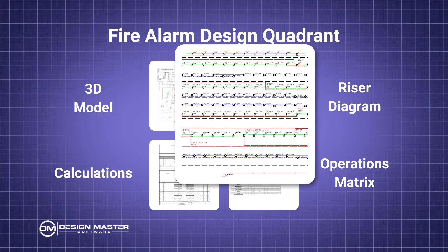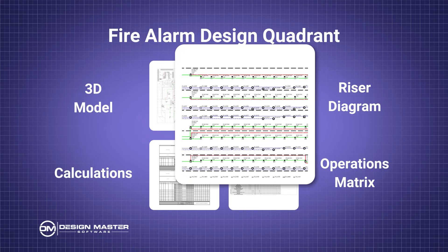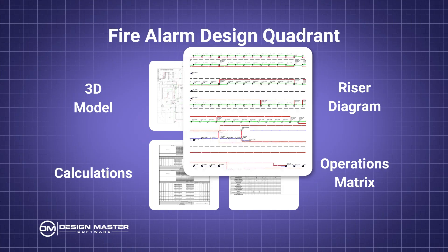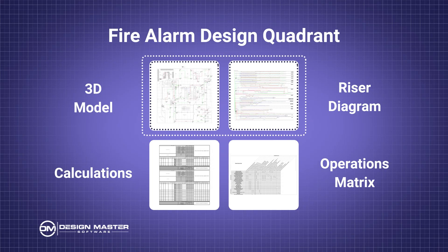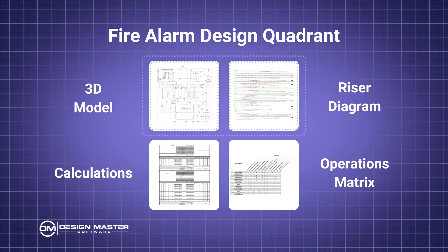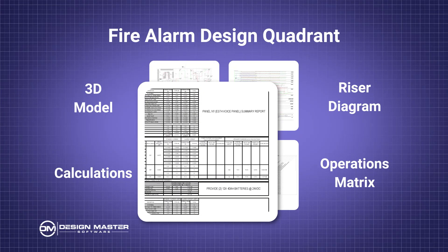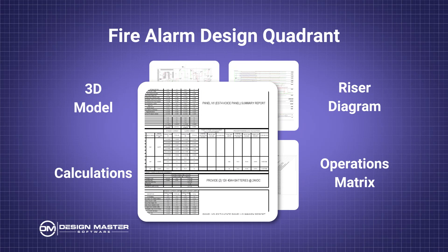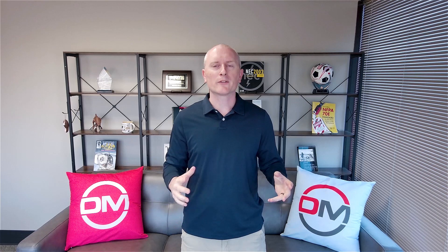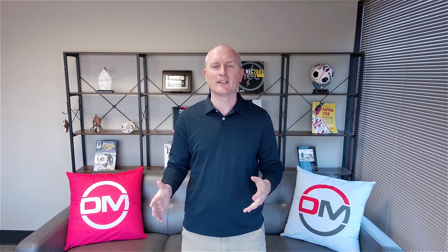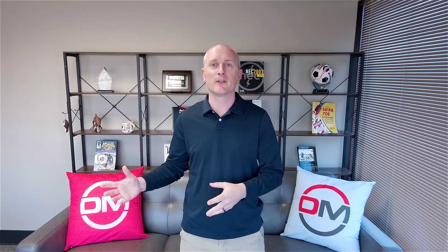The riser is a representation of what you're doing on the plan view, just as a diagram. That needs to be integrated with what you are doing on the floor plan in your 3D model. For calculations, you're generally thinking about voltage drop and battery calcs — those are the two calculations that you need at the design stage to hand to the plan reviewer to get your permits.